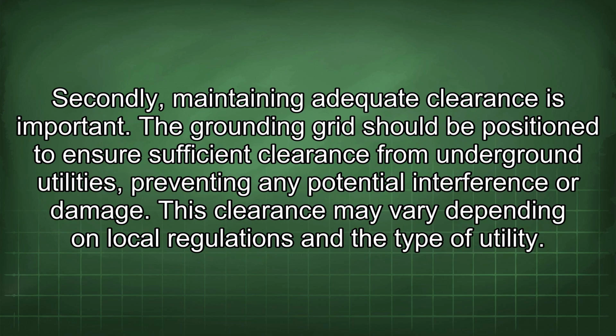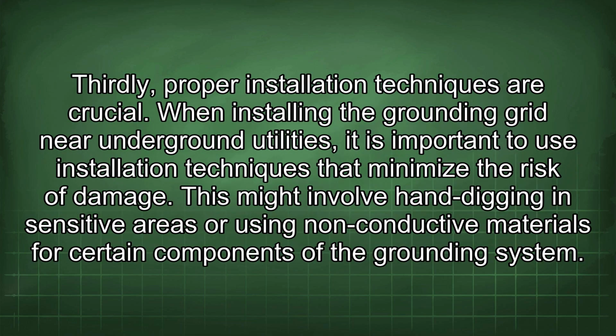Secondly, maintaining adequate clearance is important. The grounding grid should be positioned to ensure sufficient clearance from underground utilities, preventing any potential interference or damage. This clearance may vary depending on local regulations and the type of utility. Thirdly, proper installation techniques are crucial. When installing the grounding grid near underground utilities, it is important to use installation techniques that minimize the risk of damage. This might involve hand digging in sensitive areas or using non-conductive materials for certain components of the grounding system.